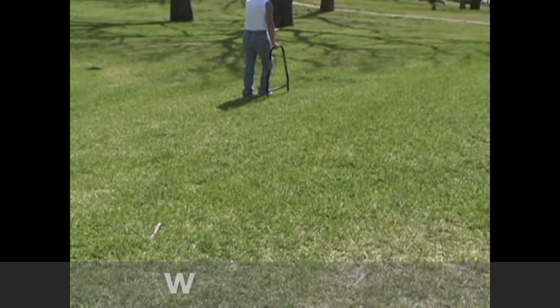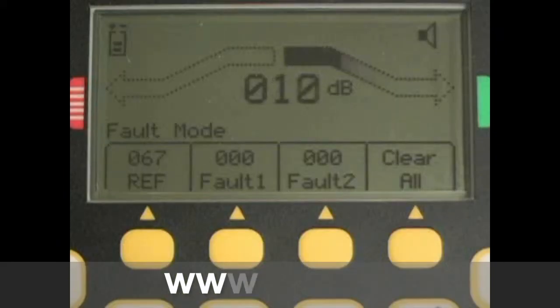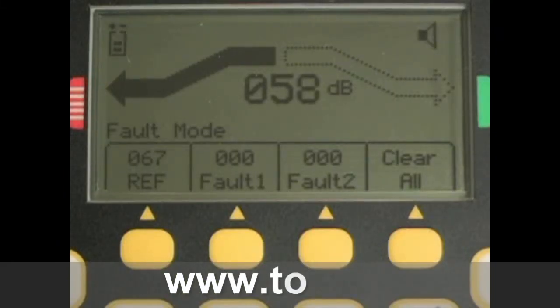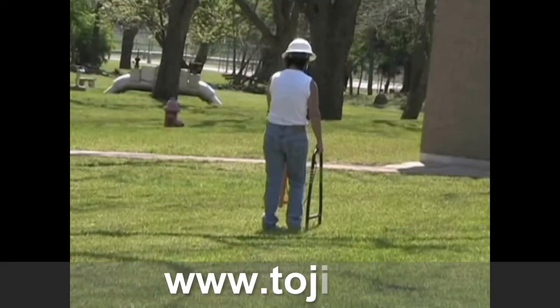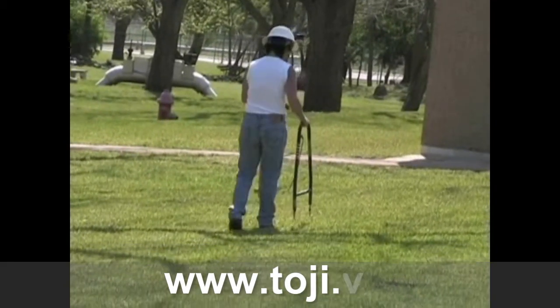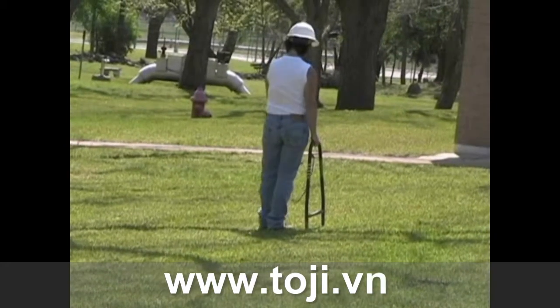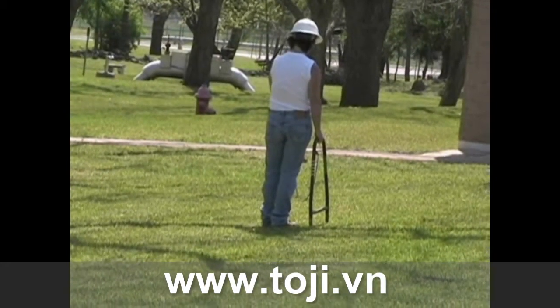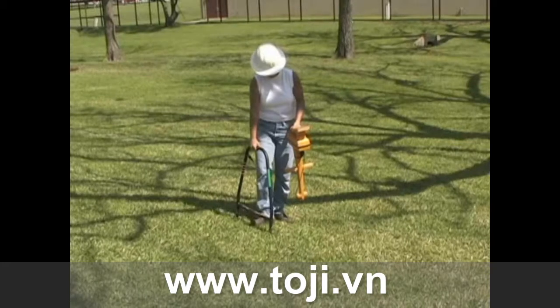Divide the section into pieces and continue probing the ground until the arrow reverses. The receiver now points toward the red band on the left side of the screen, indicating that the red leg is now closer to the fault. Probe the ground back and forth until the fault is centered between the red and green legs of the A-frame. You have now located the fault two-dimensionally.